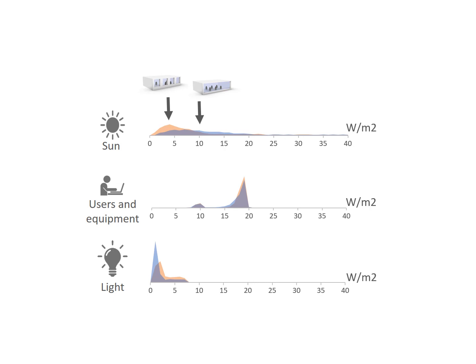We could improve the design with higher solar heat by improving the solar shading system. We could, however, also try to decrease the dominating heat load, the user and equipment load, demanding lower user density in the office room. The heat load caused by light is very little in both designs. Improving the lighting system or daylight availability would not affect the thermal comfort remarkably in these cases and could be neglected in further design development.